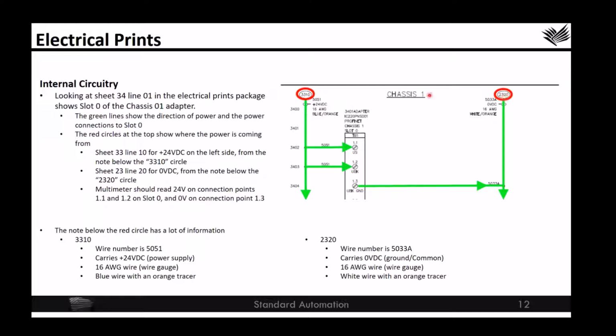If I was to hook up a multimeter to chassis 1, slot 0 at connection point 1.1 and 1.2, I would expect them to read 24 volts. If I was to put a multimeter up to connection point 1.3, I would expect to see 0 volts or ground or common. Under 3310, we see that the wire number is 5051. It's carrying 24 DC volts.